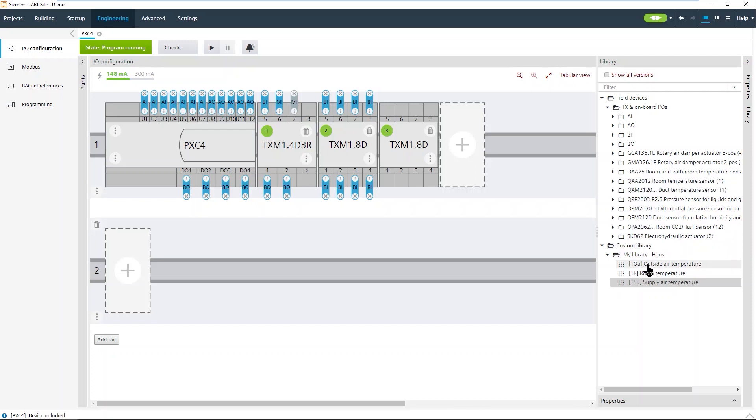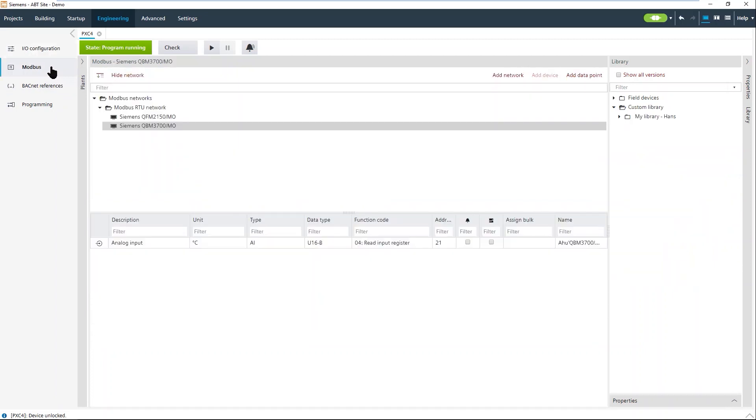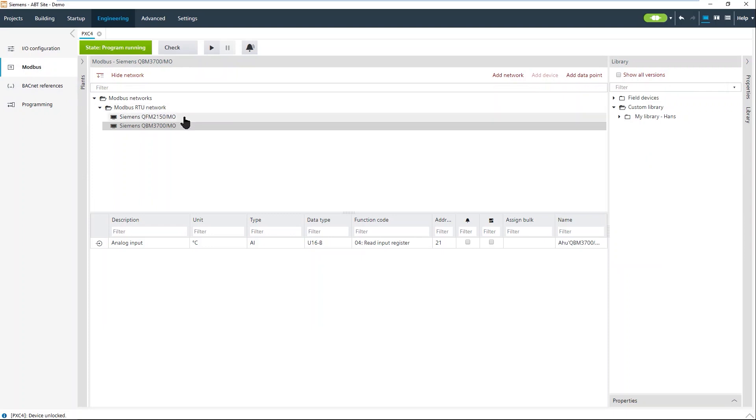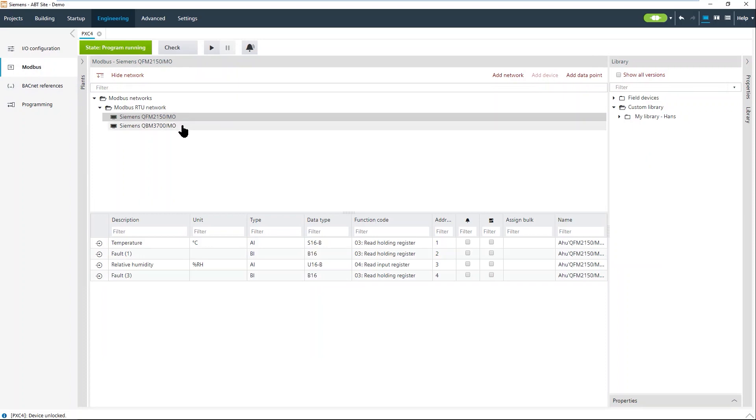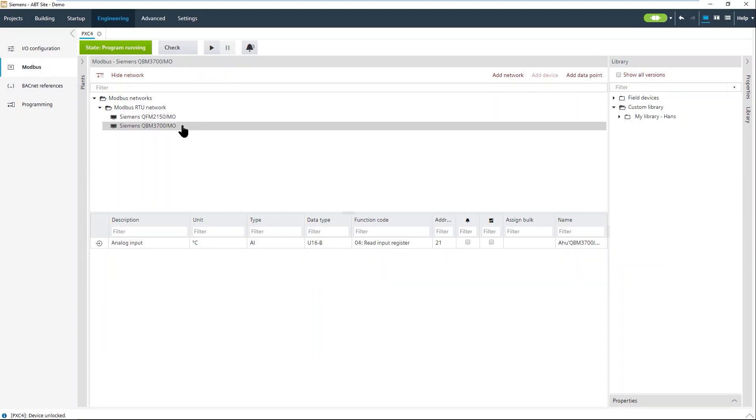What is very nice with the new PXC4 controller, we have a Modbus interface embedded. We have a Modbus editor. You can make a Modbus network. We have the Modbus TCP network and we have the Modbus RTU network. You can add the network and here you can add very easily Modbus devices. Modbus data points are treated exactly the same as physical data points so that you can use them in your program.